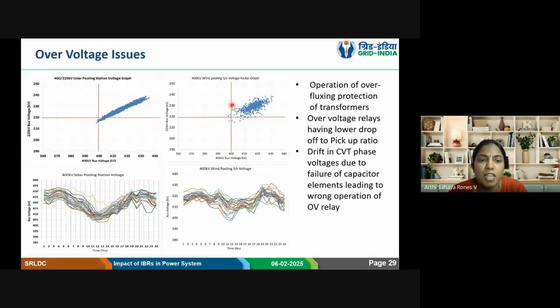On the 400 kV side, as I said, we have a graded over voltage protection, because when the voltage goes above 110%, we don't want all the lines connected to that particular substation to get tripped. Whenever one line gets tripped, based on the reactive power relief, the voltage will come down so that the other lines can stay in service. Most of the time, these line over voltage protections are very sensitive. They do not have a high drop off to pickup ratio. Because of that, some maloperations can happen.